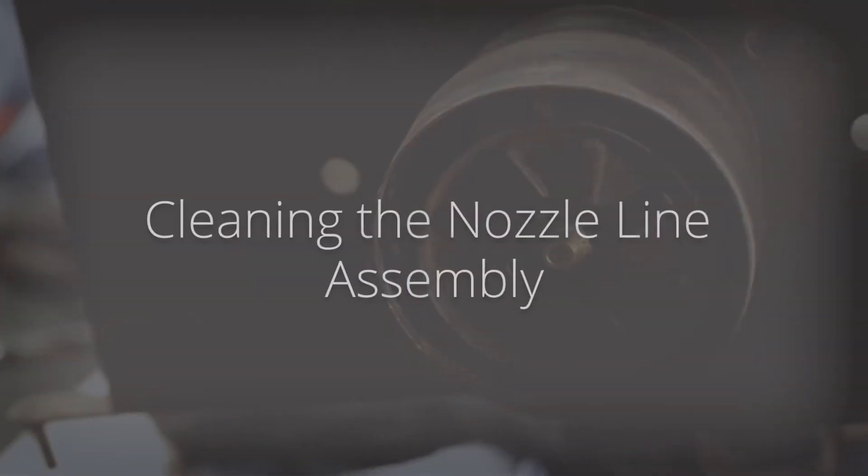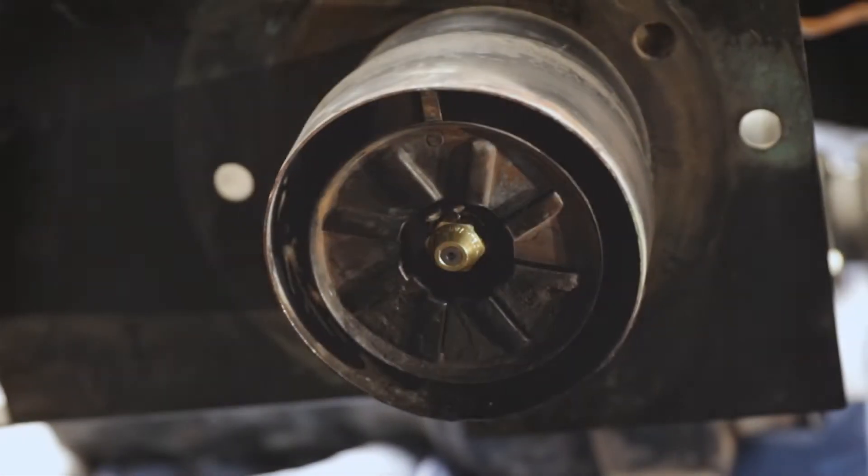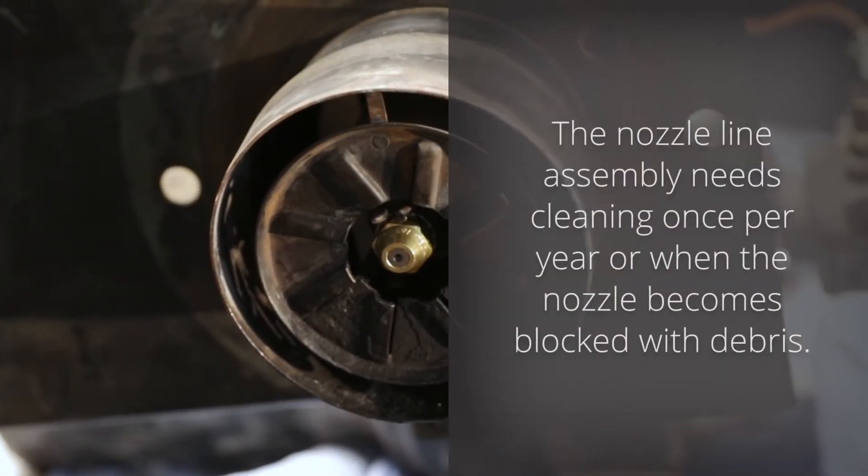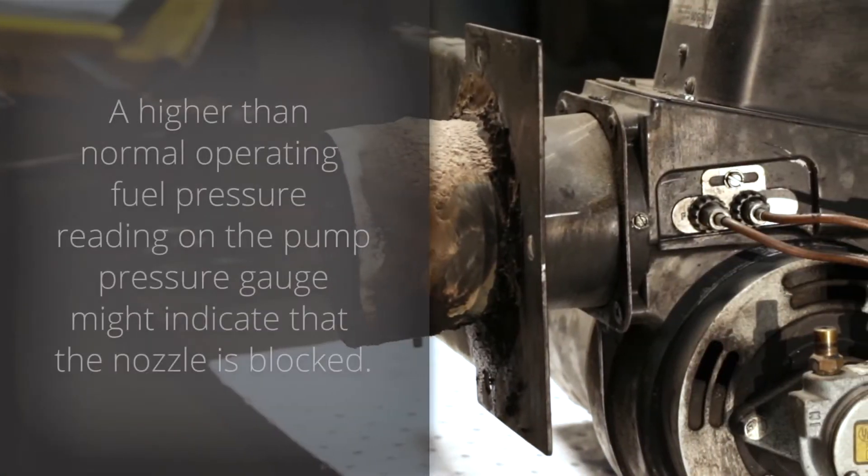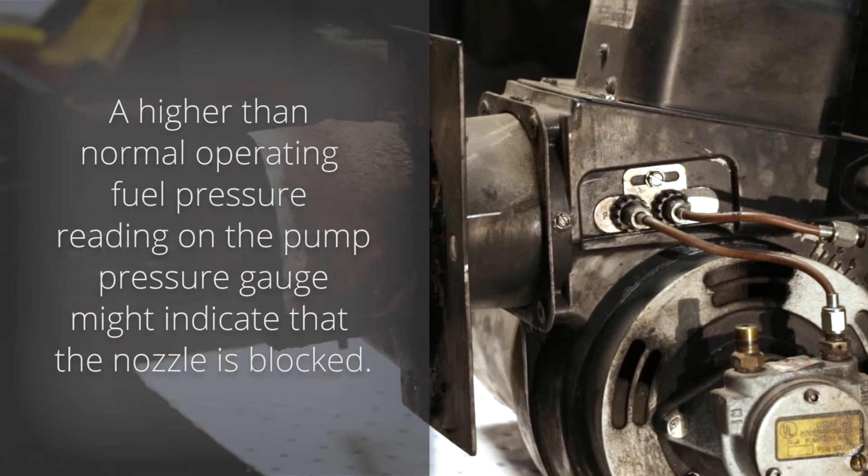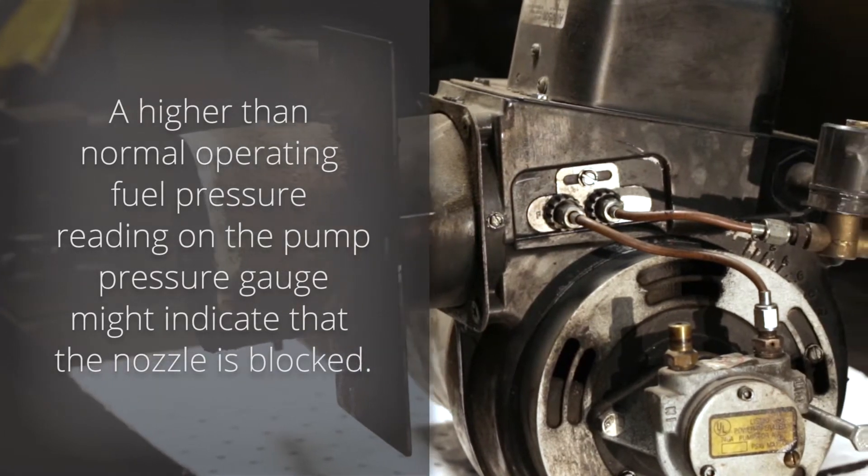In this video, we'll explain how to clean the nozzle line assembly in your EnergyLogic waste oil heater. The nozzle line assembly needs cleaning once per year or when the nozzle becomes blocked with debris. A higher than normal operating fuel pressure reading on the pump pressure gauge might indicate that the nozzle is blocked.